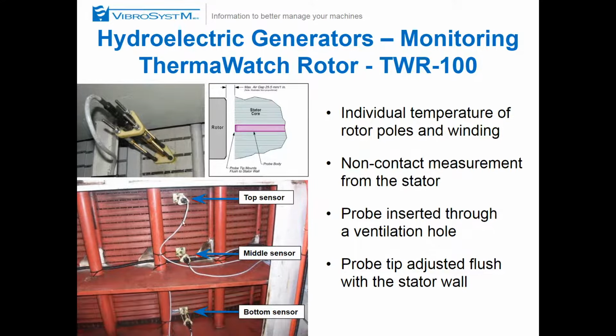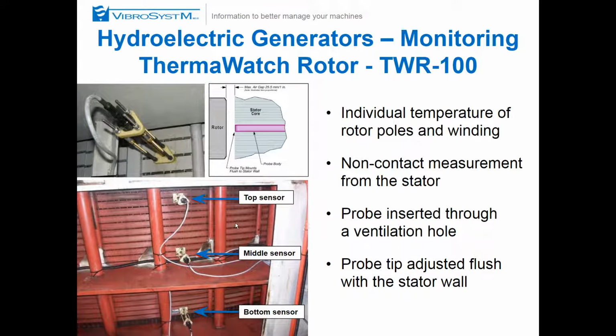So we have an example here in Eastern Canada where you can see that three sensors were installed. This unit had been uprated, and that's probably the most popular use for this technology: units that have replaced the turbine and increased the power output anywhere from 2 to 5, 6, 7%, increasing the electromagnetic stress in the air gap, and the poles will overheat. Well, they will heat more. They will be subjected to more heat. The question is how much, and is it too much? And these sensors can tell you if that's the case.